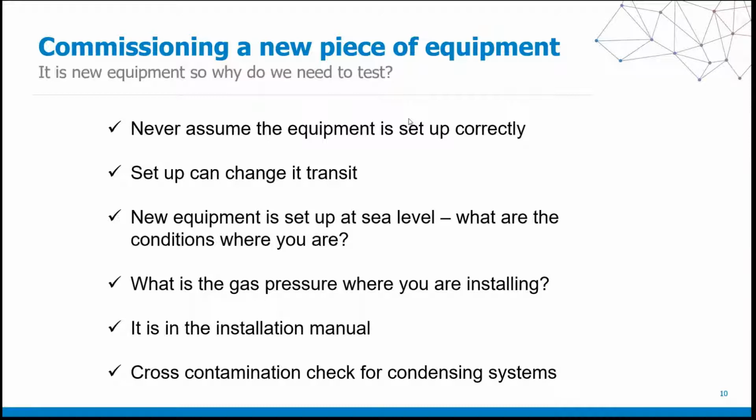New equipment is also set up at sea level. Where do you live? What are the conditions where you're at? Are you at atmosphere? What elevation are you at? So you need to account for that. Are you installing in Denver, and this device was set up at sea level? You need to understand those conditions and set the piece of equipment up accordingly.